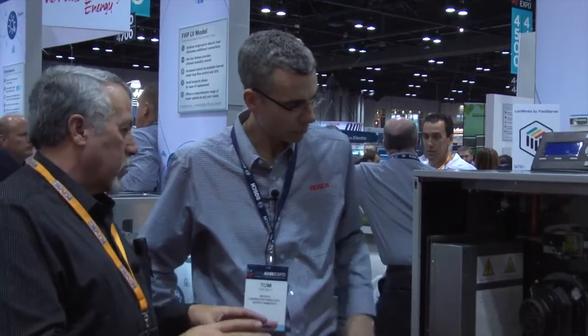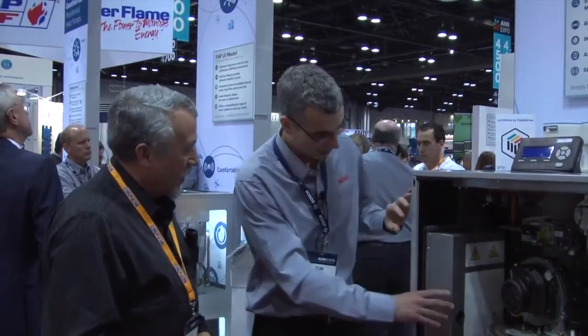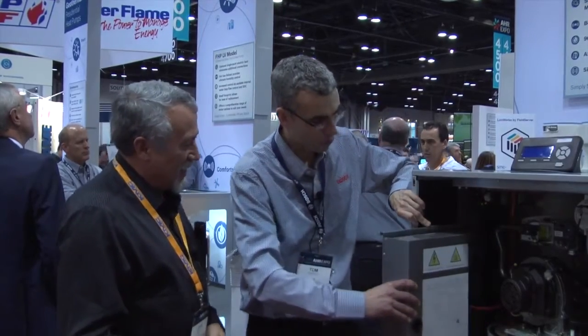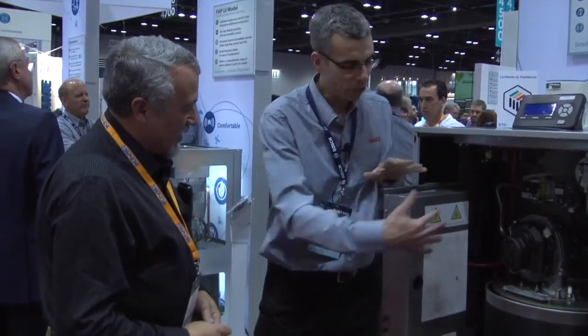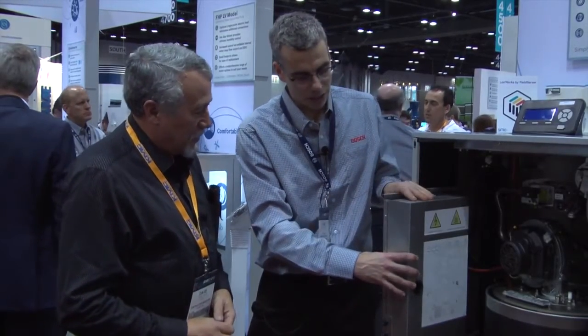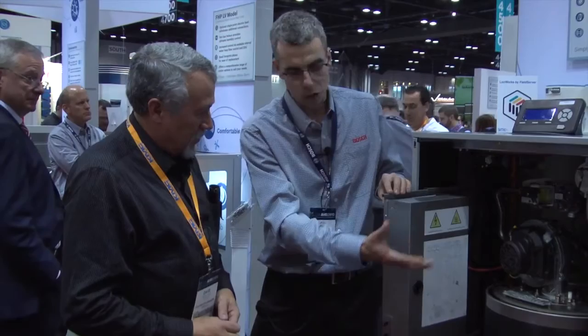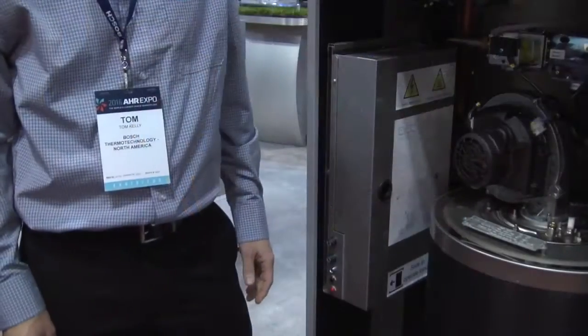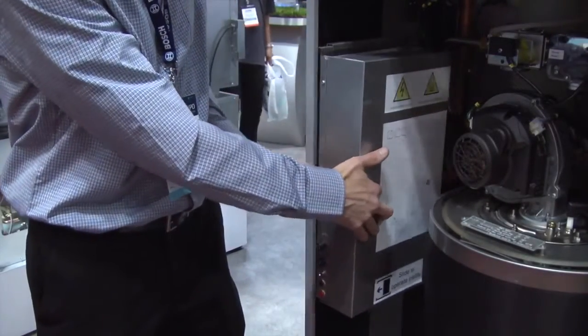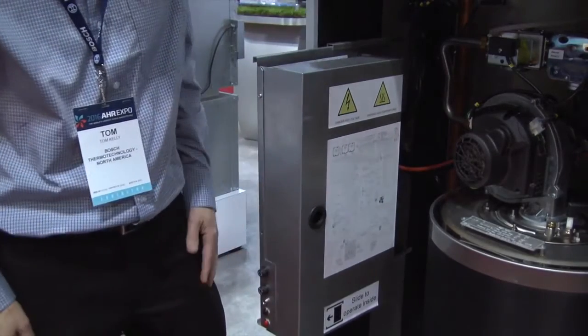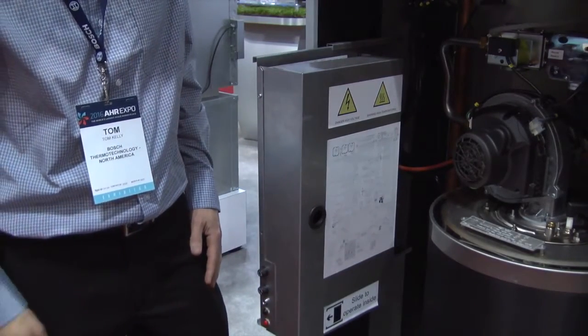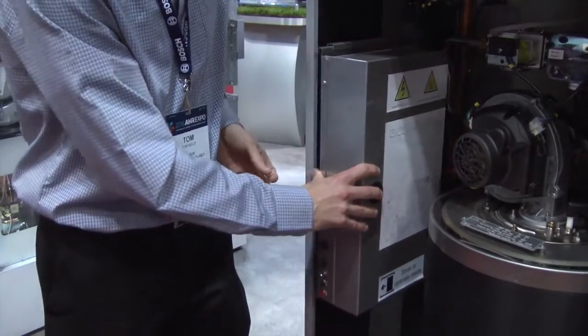I like the fact that as an installer, technician, and designer, there's room in here for our techs to work without having to take 15 other components out of the way first. Oh, another feature about that? I was just going to ask you about this. This control slides out, so you don't have to reach in here, you don't have to work in tight spaces. This control board slides out. Two screws would allow you to take this control board off, and then you have access to all your line and low voltage wiring. All wiring will come into the back, and we have knockouts on the left and the right side for easily chasing and securing your wiring through.